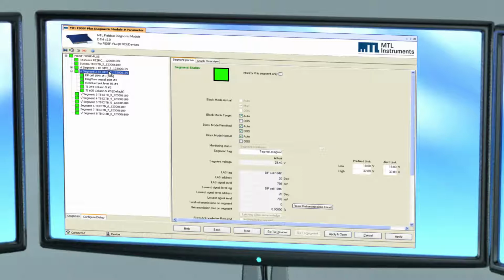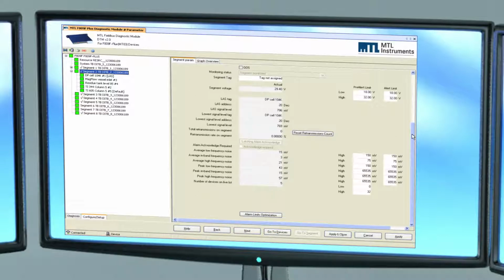The diagnostic parameters for individual segments may be viewed by opening their segment transducer block, in this case segment 2. Here we see parameters such as the segment voltage and the device tag and lowest signal level of any device on the segment. Total retransmissions on the segment since the last reset are also displayed.